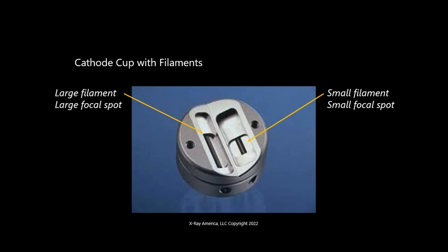Well, it's an interesting point. Now, the IEC spec for that, which is 60336, if I'm not mistaken, allows 50% variation. Oh, wow. So the 0.6 can be up to 0.9. That's huge. Yeah, and we can see visually a 30% change. Right, that's just the standard, that's why. And they see a visual difference.